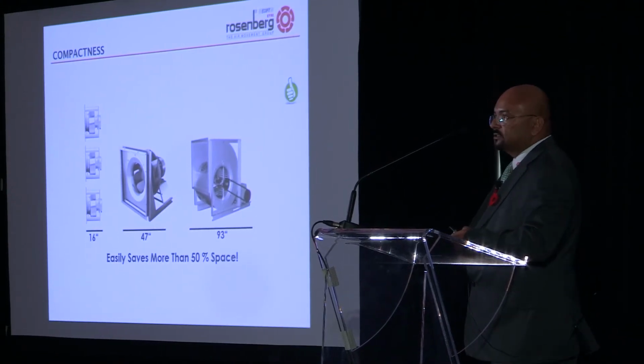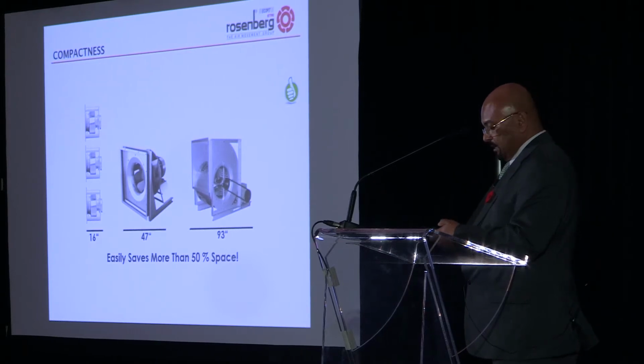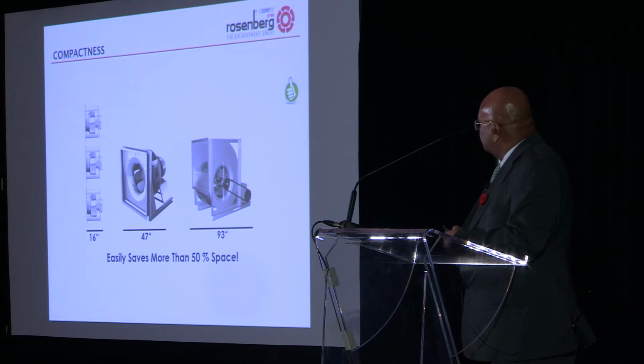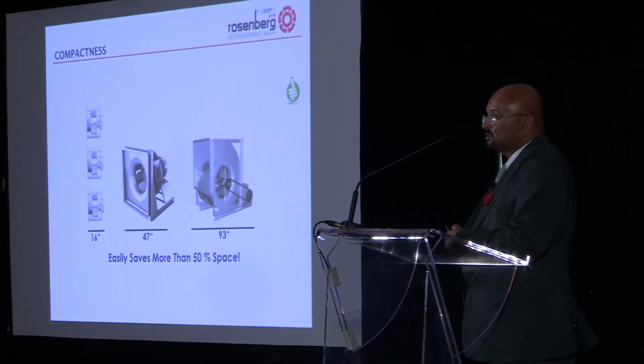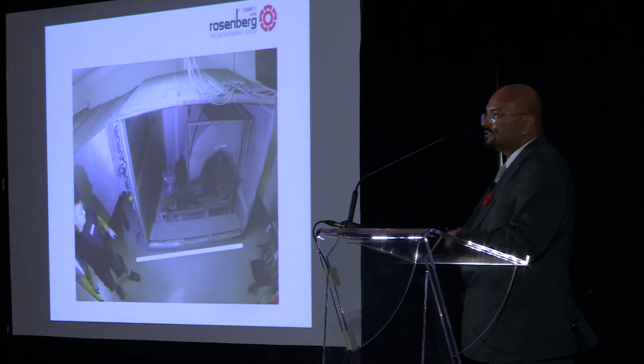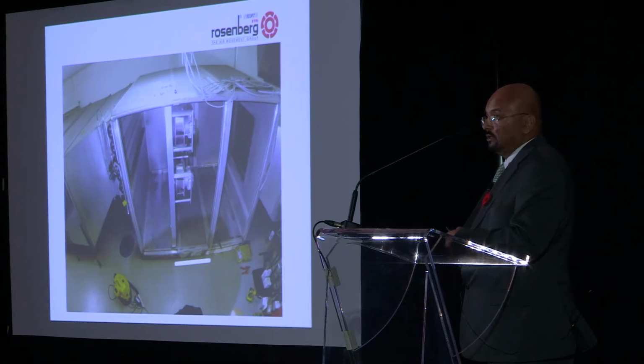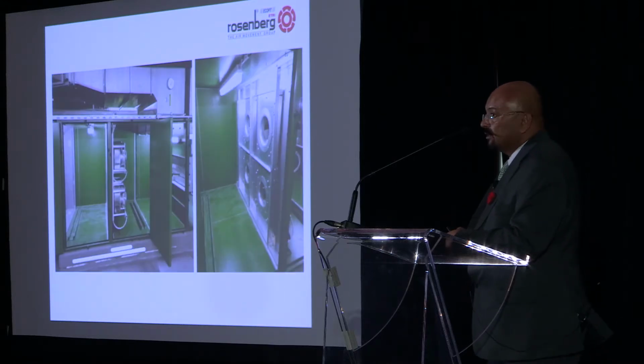The third thing is compactness. Our fans, as you can see on the left-hand side, are almost a quarter the size of the single fan. For the single fan, we just mentioned a number, which is 93 inches compared to 16 inches. So it's so much more compact. It takes less space. That's the whole idea. This is a perfect example of what we show here. It's a single fan. Look at the space it's taking inside the casing. And then compare with what we use. This is the fan grid, right? It's taking much less space, and you can utilize the space by adding more equipment, right? This is how it looks after the retrofit installation. You can always utilize this space for any other equipment.